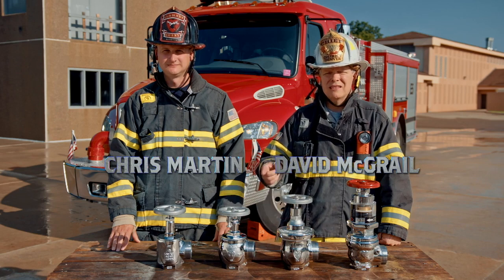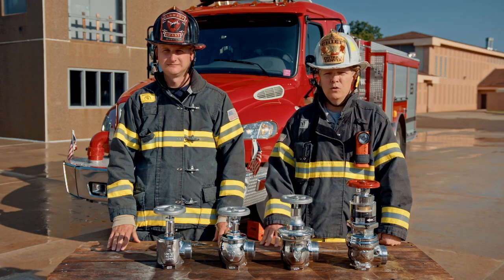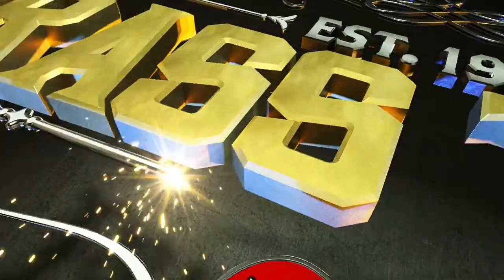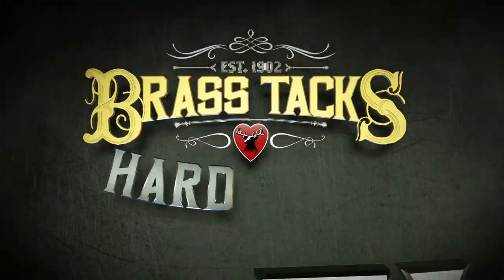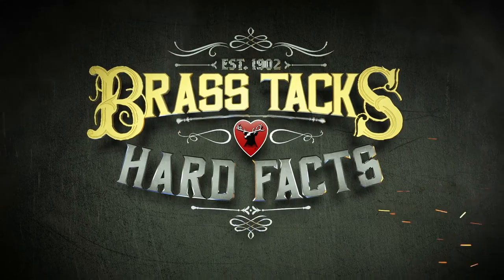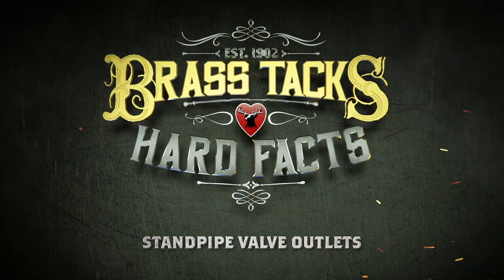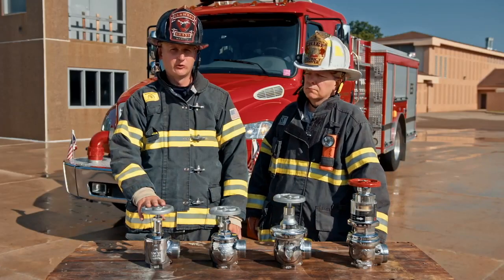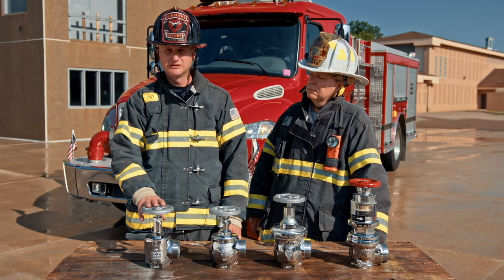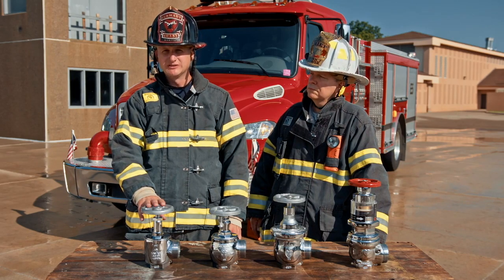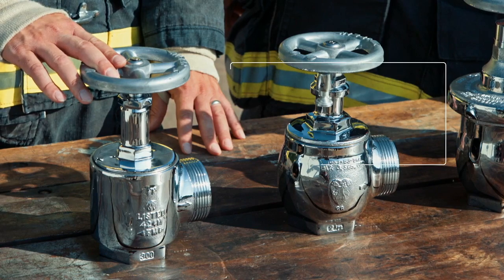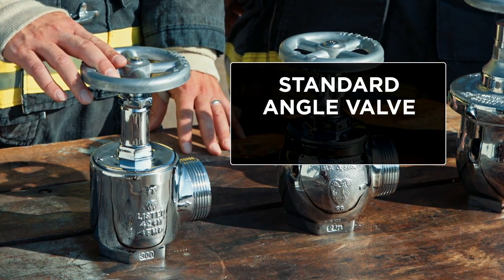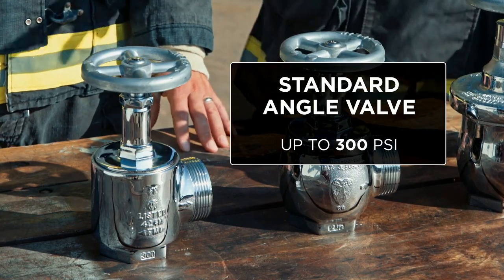And we're getting down to the brass tacks and hard facts of standpipe hose valve outlets. We're going to review the 4 common types of standpipe valve outlets, some design and operational considerations. The first type is a standard angle valve. This type of valve would be found in uppermost floors, and it's rated for PSI up to 300.